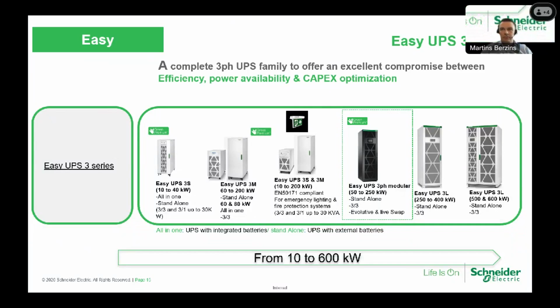So to start the presentation, this new launch, the new Easy UPS modular, is under our Easy UPS 3 range category or family, which we started around 4 years ago with the Easy UPS 3S products from 10 to 40 kilowatts, which became a highly popular product in the Baltics and in Europe. We also launched Easy UPS 3M, a version for medium power ratings from 60 to 200 kilowatts. And with the Easy family, we also have dedicated UPSs for emergency light and fire protection systems, which are EN 50171 compliant. Then around 2 years back, we launched the Easy UPS 3L versions from 250 to 600 kilowatts.